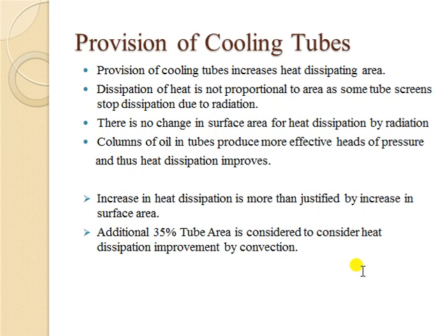Provision of cooling tubes increases the heat-dissipating area — earlier we considered only the area of the plane tank, but now we additionally consider the area of the tubes. However, tubes act as a hindrance to radiation between the tank surface and the external environment, so in tubes there is no radiation heat exchange — only convection. On the positive side, columns of oil in the tubes produce more effective pressure heads, improving heat dissipation. This improvement is more than justified by the increase in surface area, so an additional 35% of tube area is considered for convection-based heat dissipation improvement.